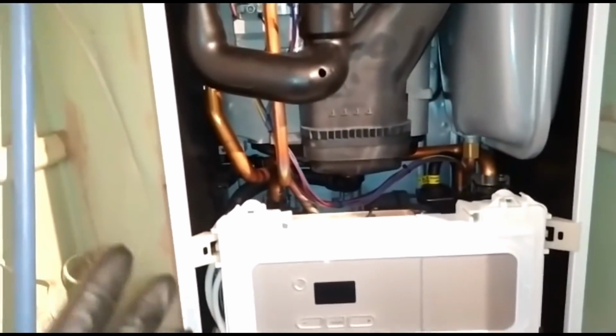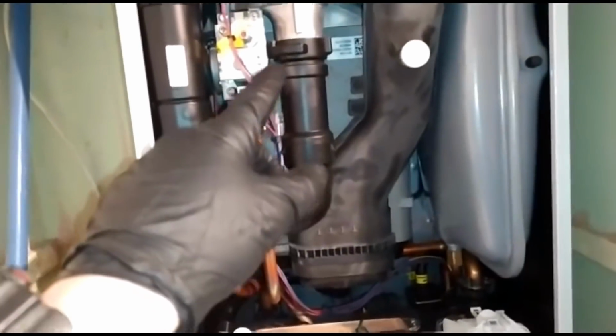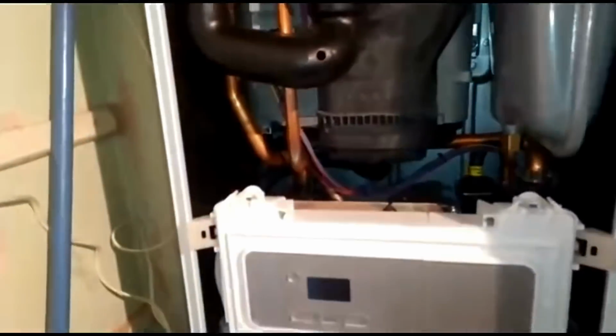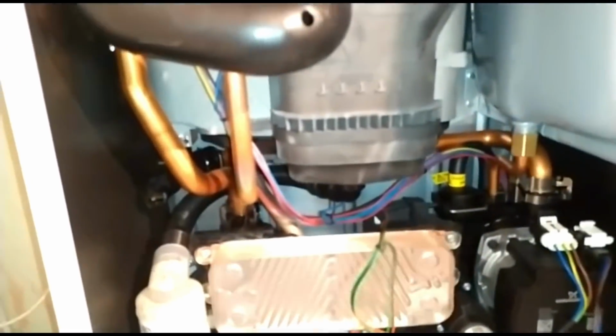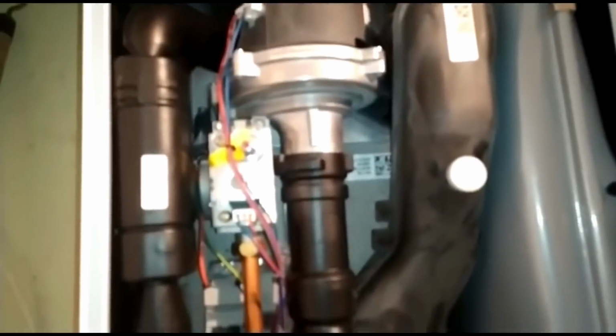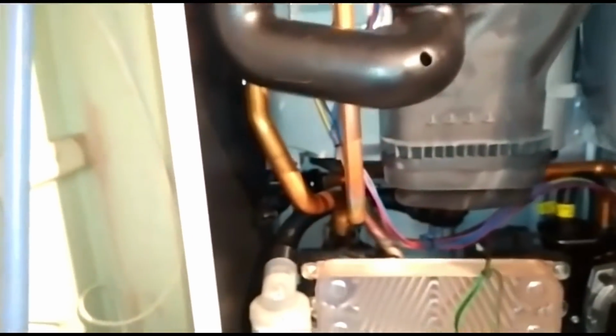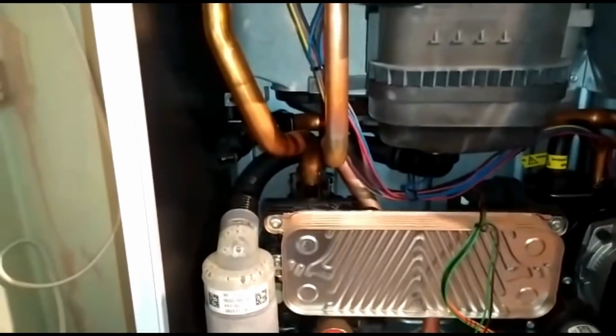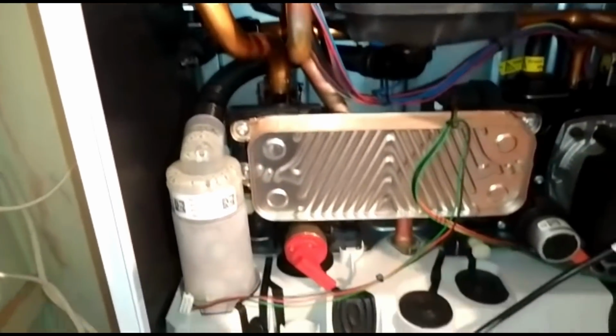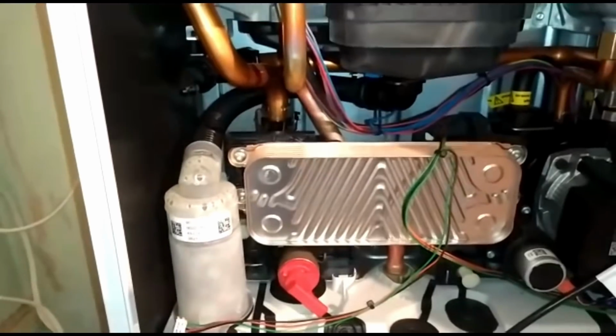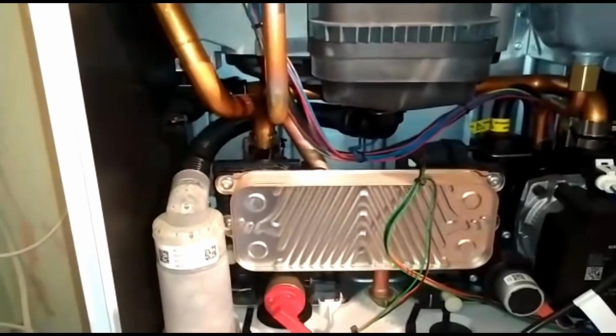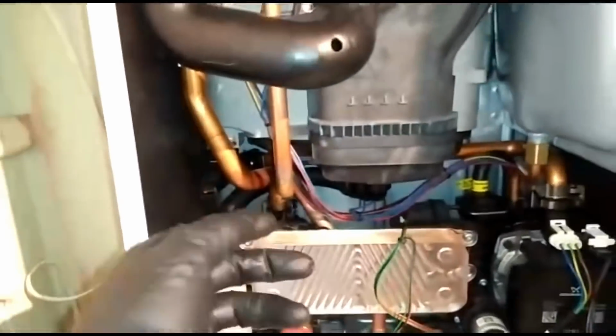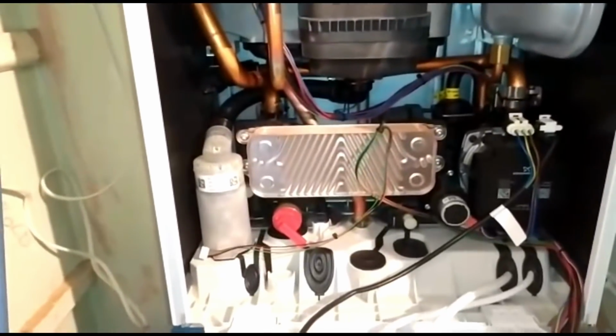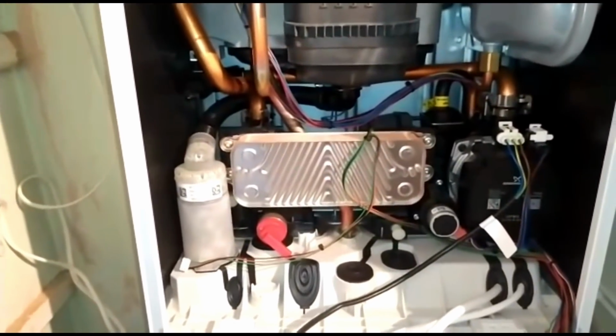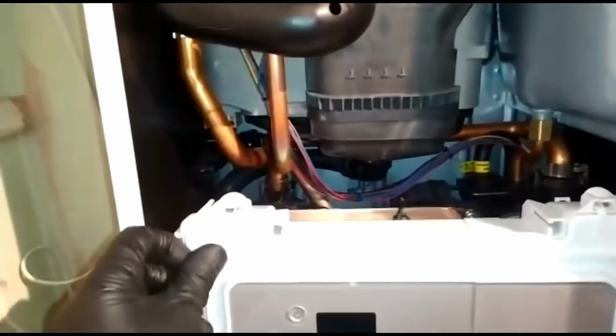Same on the boilers, just because I've serviced it doesn't mean the gas valve's not going to go a week later or the fan's going to go the following day. But other than just the gas safety side of it, it does protect the boiler, it does give you less chance of having a breakdown. It's freezing cold, it's been snowing, not a lot because we're down in the south, but by doing this I know chances are, well I know, by changing that they're not going to have an issue with that particular part of the boiler. So yeah, just the importance of carrying out your boiler servicing.